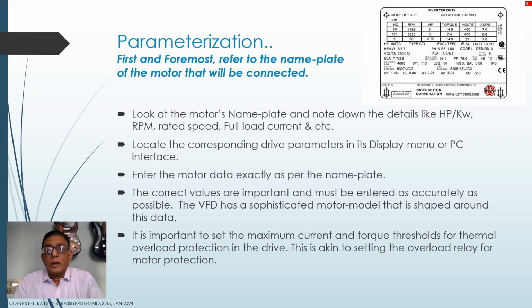Then, above all, it is very important to set the maximum current and torque threshold. These parameters will be effective in overload protection, that is, the equivalent of a thermal overload tripping. This is the exact same thing that prevents a motor from burning away. Motors draw much heavier currents now and then, not on a sustained basis. So this has to be done according to the motor nameplate current. Fine.